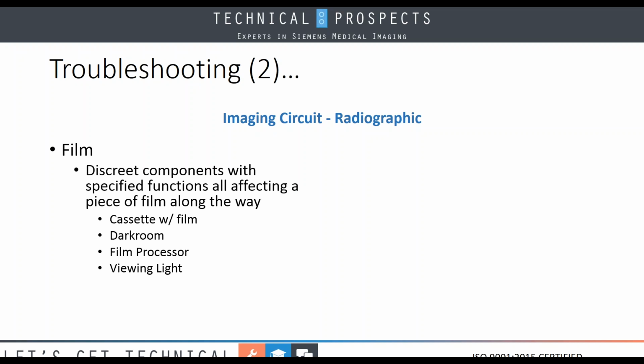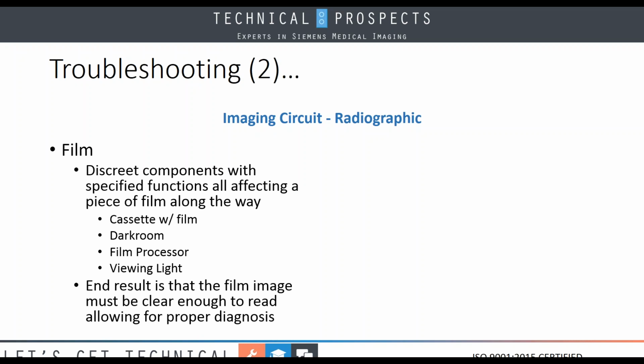Also, our viewing lights. Are we getting the proper amount of light on the light boxes? This is something that should be checked on PMs. And back in the older days, we had hot lights that were really intense lights to help us see even more clearly. The end result of all of this is that the film image must be clear enough to read and allow for proper diagnosis. If it's not, we've got to do retakes.